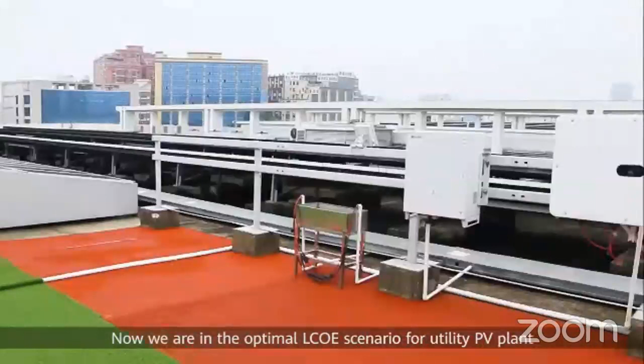Now we are in the optimal LCOE scenario for utility PV plant. In order to achieve lower LCOE, the design of 1500 volt string inverter plus bifacial module plus tracker system is highly recommended. Let's take a look at this site. Two 175 kilowatt 1500 volt inverters are installed. Each inverter is connected to 2 strings. Each string has 34 pieces of 310 watt N-type monocrystalline half-cut cell bifacial dual glass modules in series, installed on the single axis tracker.